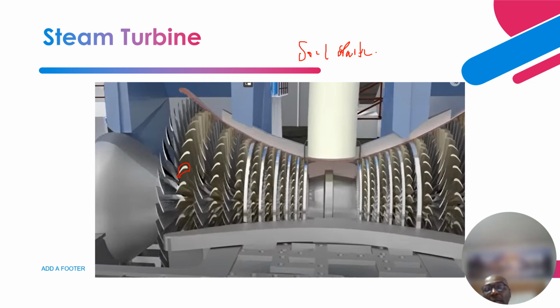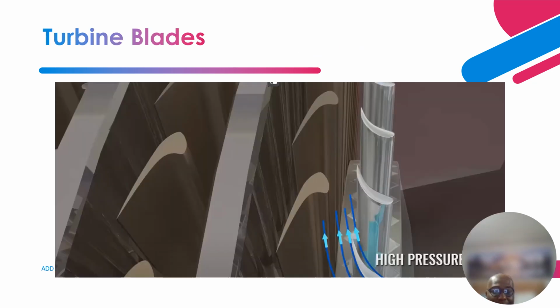And also there's something they call root blade cracking. These blades are embedded in the shaft, and with time they crack. So the shape is created in this form so that it minimizes the cracking that develops with time as the steam turbine is in operation. Okay, so like I told you, this is the tip of the turbine blade, and it's in the form of an aerofoil, creating that aerodynamic high efficiency shape. So you see that the high pressure steam comes in here, and you have the rotating part. This is the blade that is rotating, and this is the stationary part.